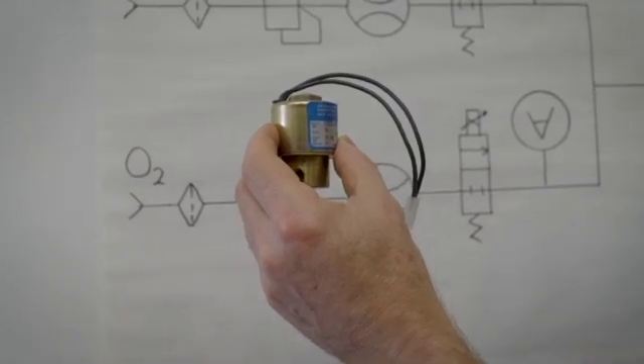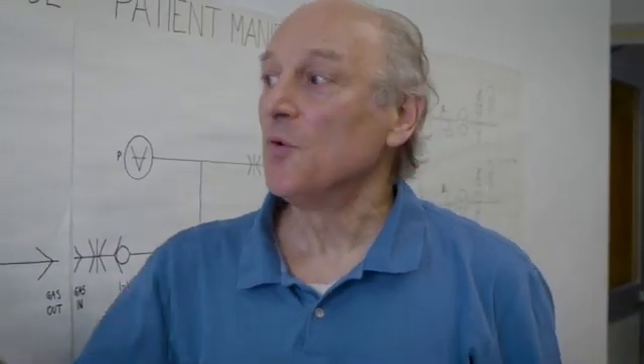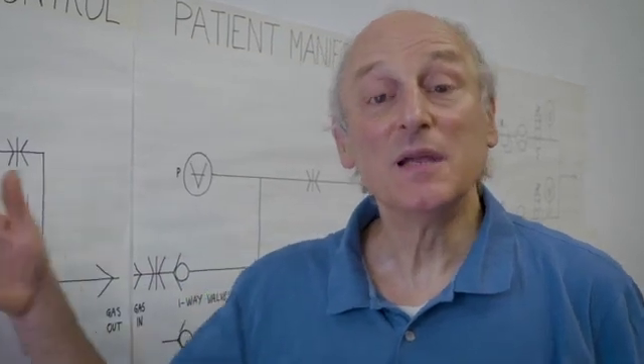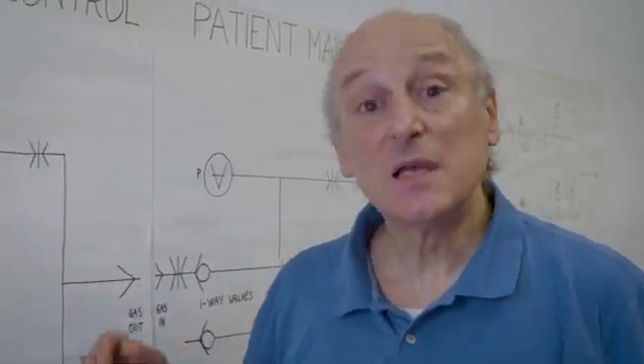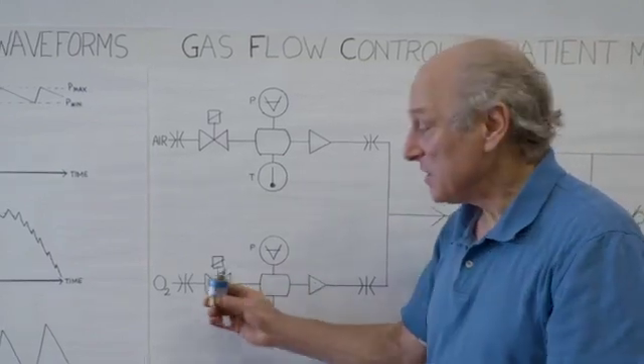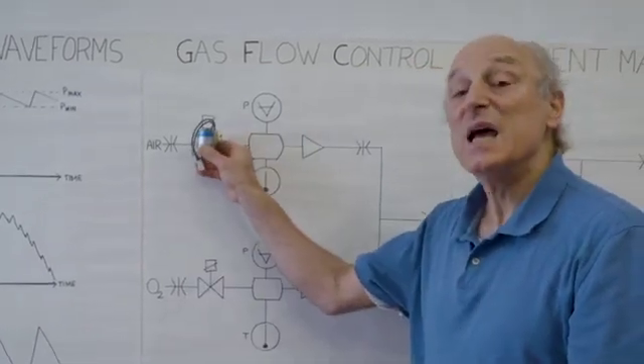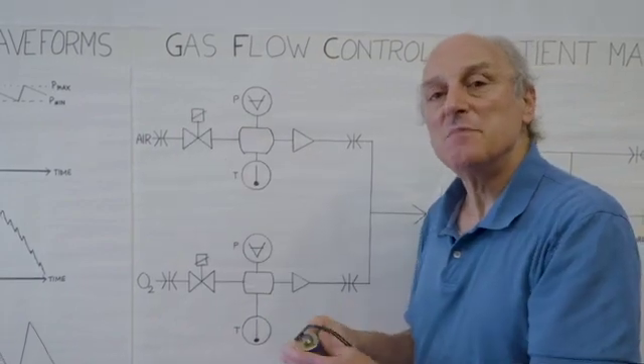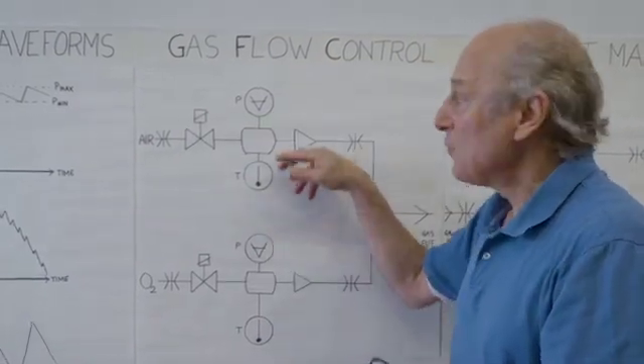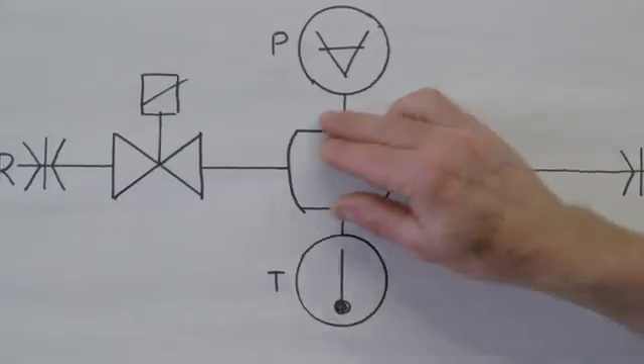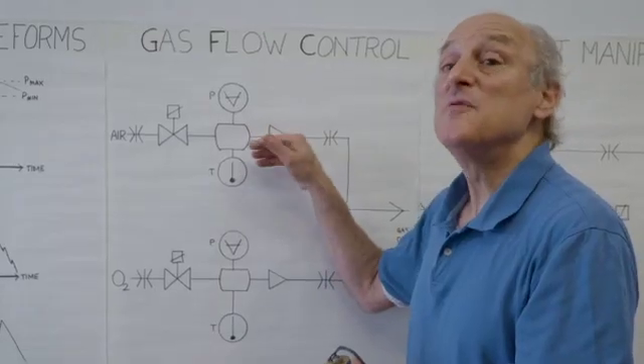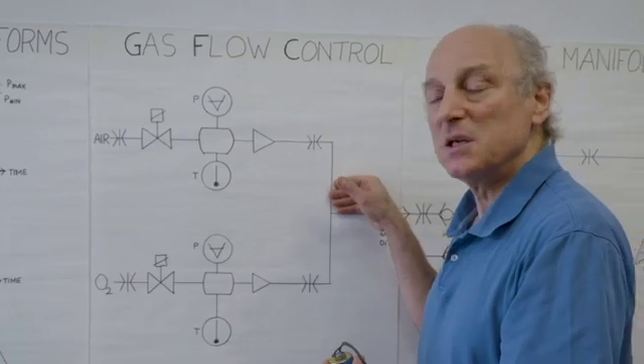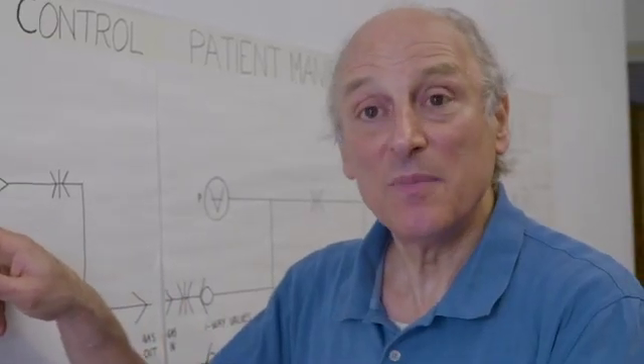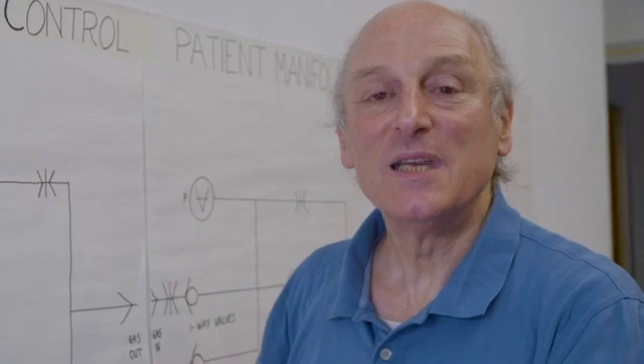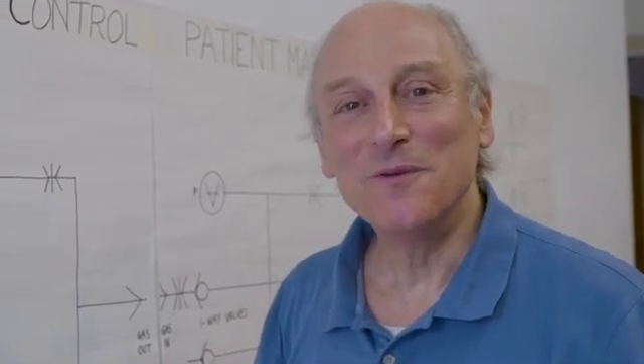single solenoid valve. In our new design, we still have air and oxygen coming in and going to the patient, and we need to control it. And remember, I mentioned our solenoid valve that we place here in the line. I also mentioned pressure sensors, and we put these in our special trick onto a separate little chamber before the gas goes on to the patient. And we use that special chamber to make medical ventilators more accurate, more reliable, and far cheaper than ever before.